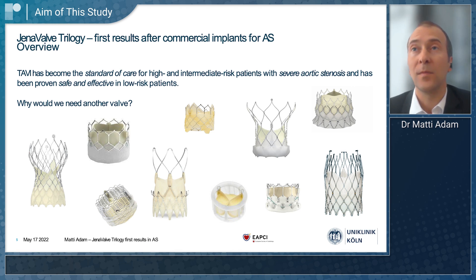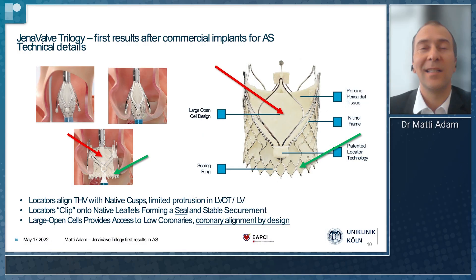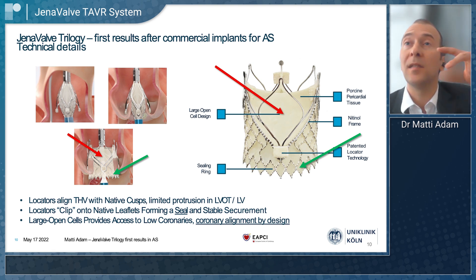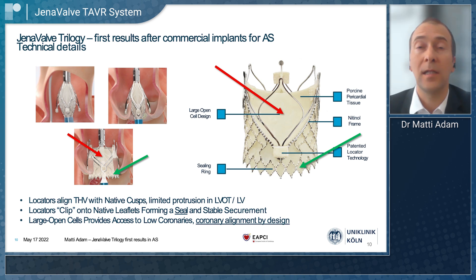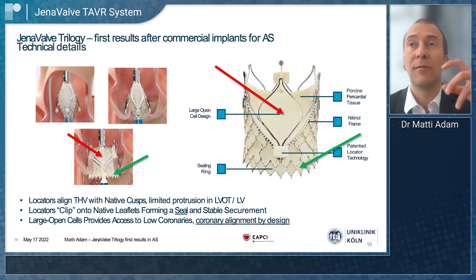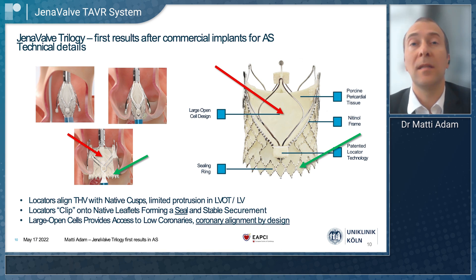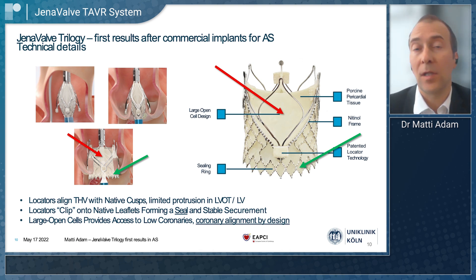We collected data from six German high-volume centers to evaluate this. The unique design features that this valve has are three locators. These three locators will go into each nadir of each coronary cusp and in each aortic valve cusp and sit there. Once the valve is expanded, the sealing ring will get into contact with the locators and basically clip on the aortic valve. This gives us the advantage of less dislocation danger, more sealing because this clipping mechanism allows more sealing, and also coronary alignment by design because these three locators go into each cusp.